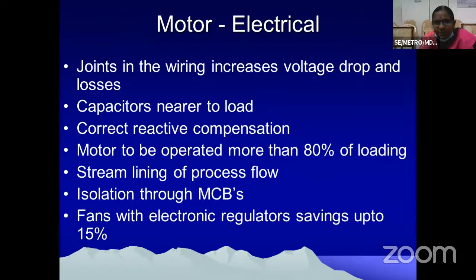Capacitors have to be provided nearer to load. In many industries, we have seen that the capacitors are provided in the mains. So overcompensation is also not much of use. So undercompensation and overcompensation should not be there. So it has to be exact. So we should provide capacitors nearer to the load in accordance with the motor capacity. That would be very, very economical and essential to conserve energy.